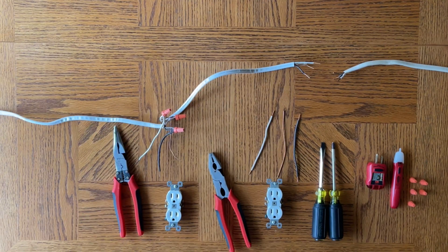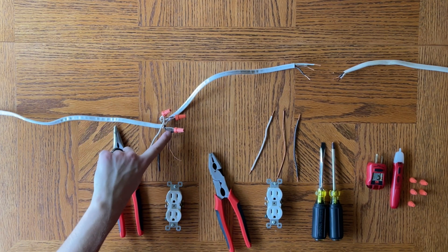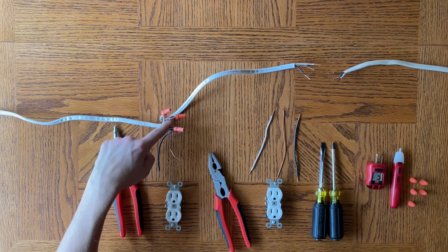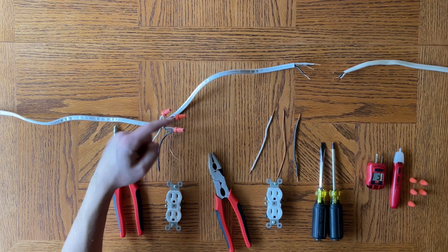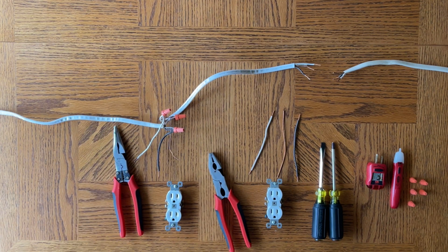Now we have these three wires wire-nutted together: the neutral, the hot, and the ground. Some people ask why waste a wire nut on the ground line since it's not insulated like the others, so you don't really need to insulate that connection. Personally, I like to wire nut everything because if you have a good wire nut tightly wound, it's not going to come apart in your box and you won't have any faulty ground line. They're cheap, they're easy, and it looks nice. In some places it might be code, so make sure you know your local codes.